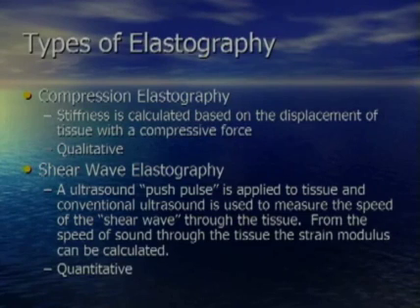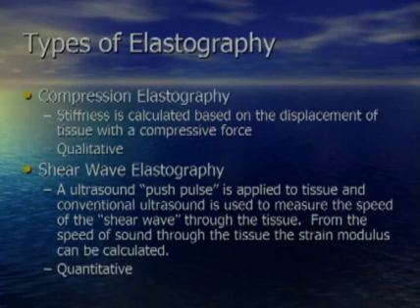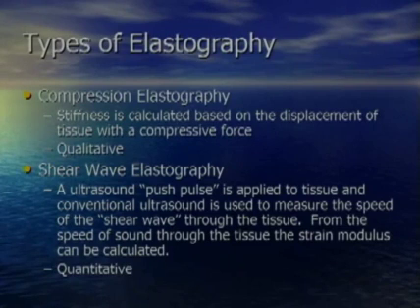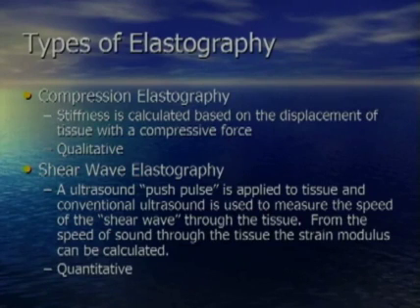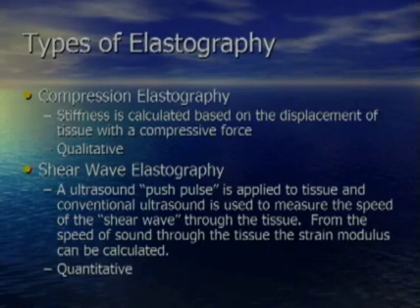The second technique is shear wave elastography. An ultrasound push pulse is applied to tissue and conventional ultrasound is used to measure the speed of the shear wave that propagates through the tissue. From this speed of sound, the strain modulus can be calculated. Since we know the amount of force applied, we can obtain a quantitative measurement of how hard or soft a tissue is.